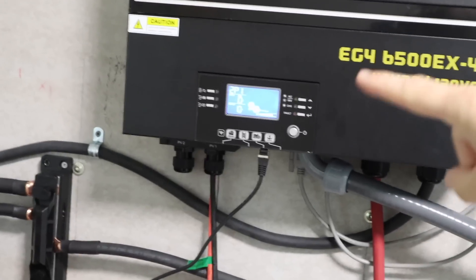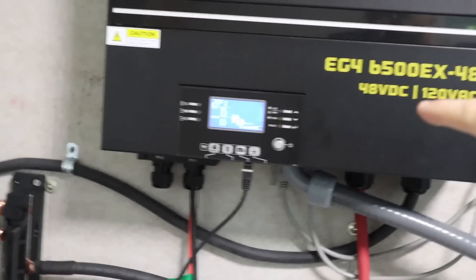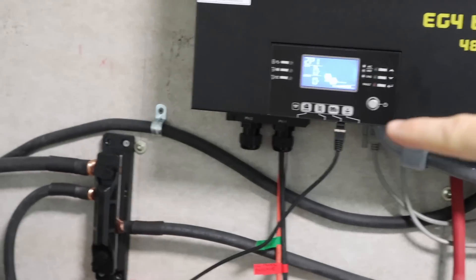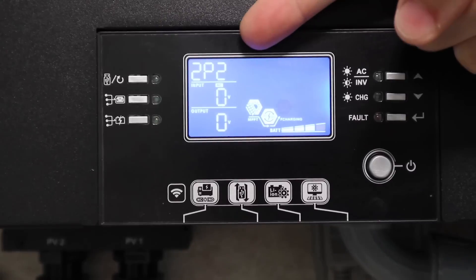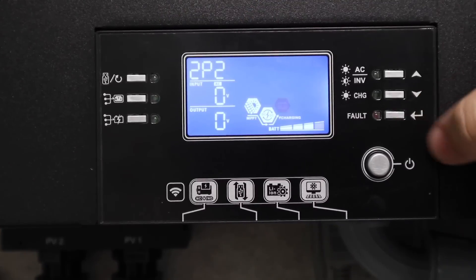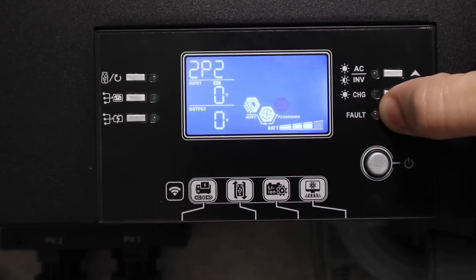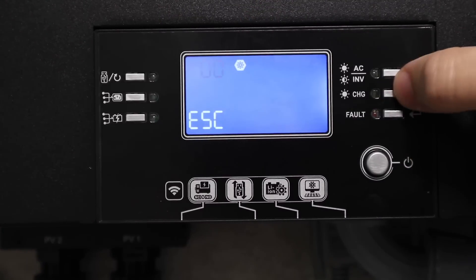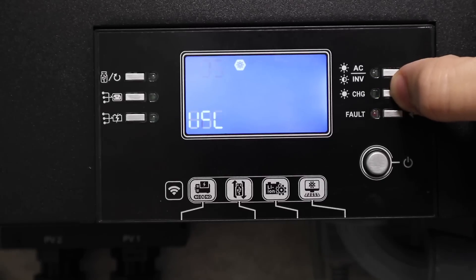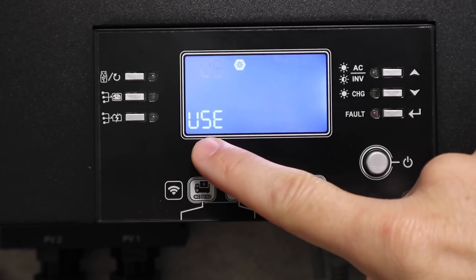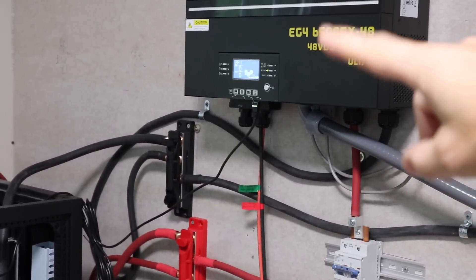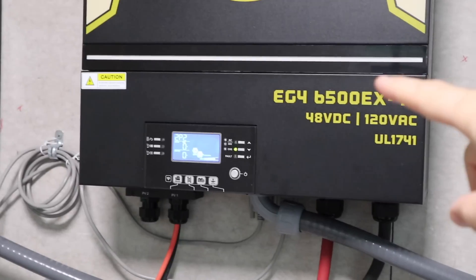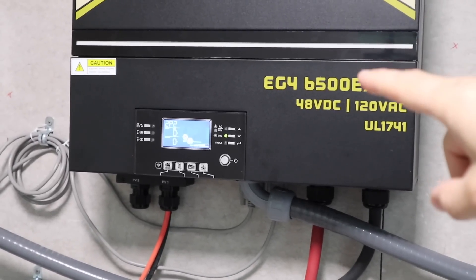If you get an error 61 flashing and beeping on your inverters, try that cable switch and it'll take care of the problem. Here on my 2P2 inverter, we are going to enter in and we are going to set the battery on protocol five to user. Remember, on your 2P1 inverter, set the battery to EG4 and any other inverter that you have paralleled to it, set it to user.